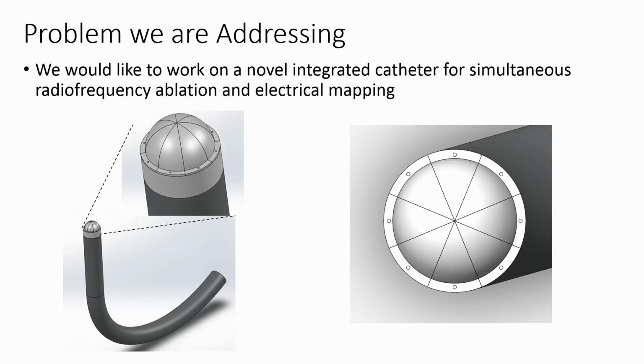So, the point is this is what we are addressing. Can we design a catheter that can perform RF ablation as well as electrical mapping both in one, and what kind of force sensor can we insert on this particular catheter?